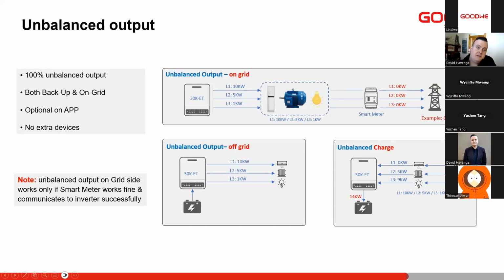One of the features that we have on our ETs is the unbalanced load output. On the off-grid output of the inverter, the backup, we always have the unbalanced output to run loads in an unbalanced manner. So we always do require neutral for the inverter so we can run these unbalanced loads. But then when we have zero export, which we do have in many countries in Africa, we're not allowed to export any power to the grid. Then normally your conventional export power limiting is either going to be lowest phase limiting or average phase limiting. When we're not allowed any export at all, then we'd use lowest phase limiting, which means your inverter will only produce on each phase the lowest consumption from utility. So then you lose a lot of energy.